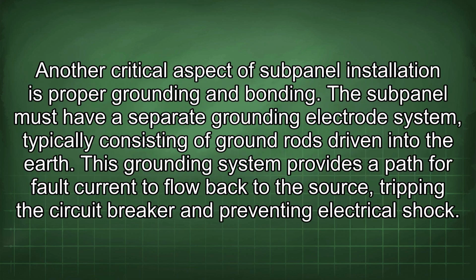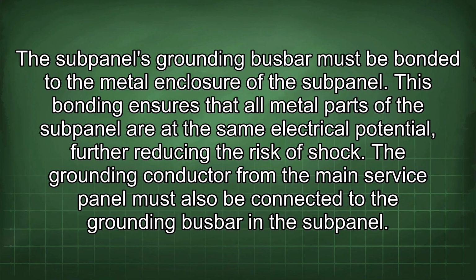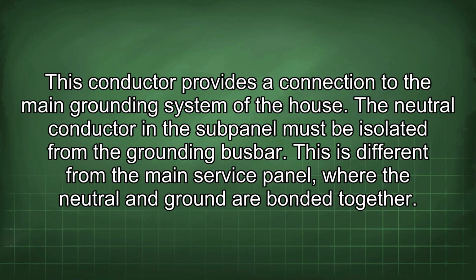Another critical aspect of subpanel installation is proper grounding and bonding. The subpanel must have a separate grounding electrode system, typically consisting of ground rods driven into the earth. This grounding system provides a path for fault current to flow back to the source, tripping the circuit breaker and preventing electrical shock. The subpanel's grounding busbar must be bonded to the metal enclosure of the subpanel. This bonding ensures that all metal parts of the subpanel are at the same electrical potential, further reducing the risk of shock. The grounding conductor from the main service panel must also be connected to the grounding busbar in the subpanel. This conductor provides a connection to the main grounding system of the house.